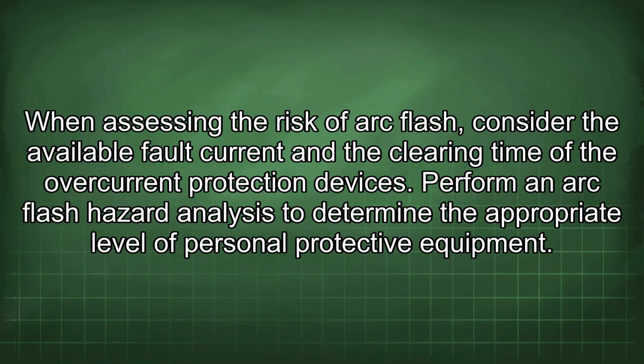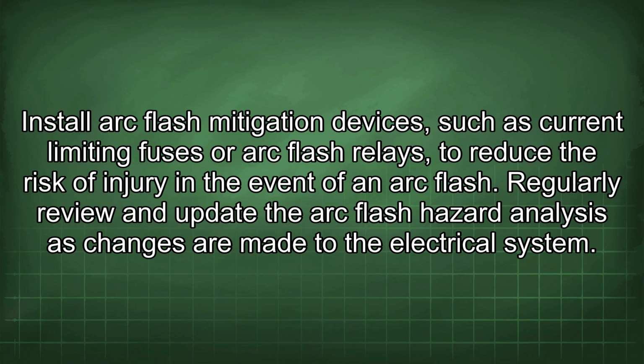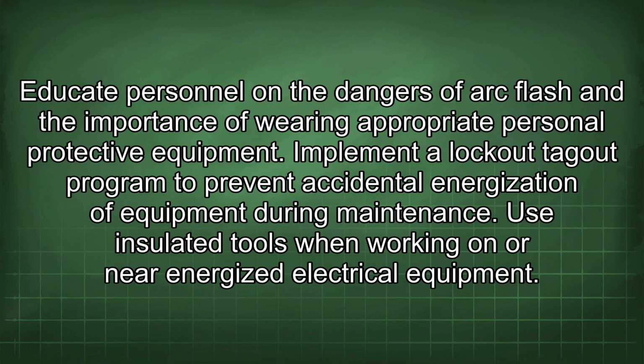When assessing the risk of arc flash, consider the available fault current and the clearing time of the overcurrent protection devices. Perform an arc flash hazard analysis to determine the appropriate level of personal protective equipment. Install arc flash mitigation devices, such as current limiting fuses or arc flash relays, to reduce the risk of injury in the event of an arc flash. Regularly review and update the arc flash hazard analysis as changes are made to the electrical system. Educate personnel on the dangers of arc flash and the importance of wearing appropriate personal protective equipment.